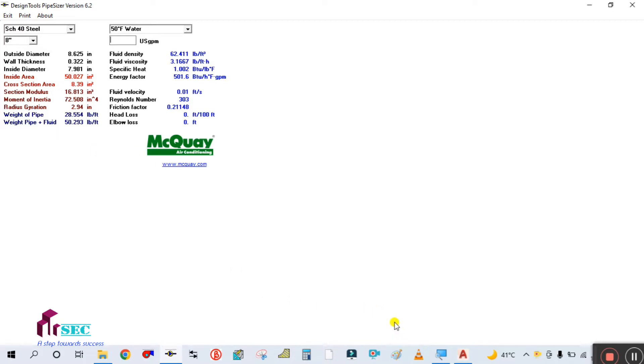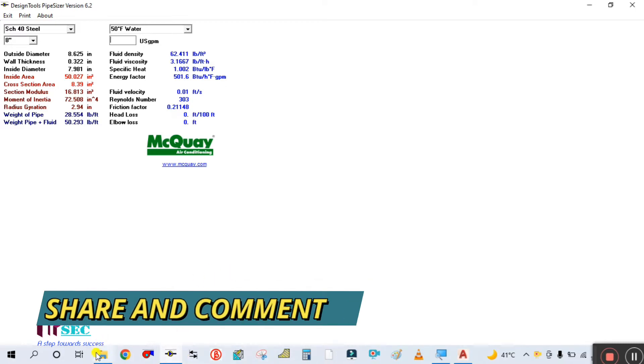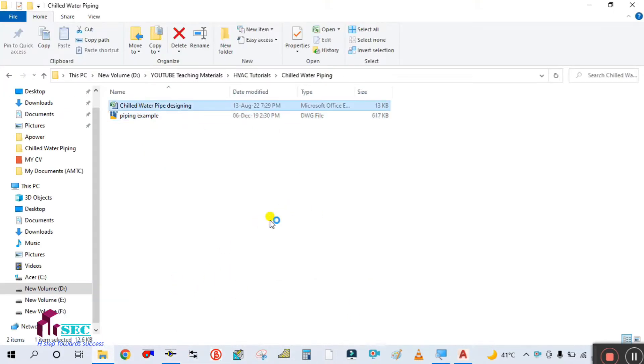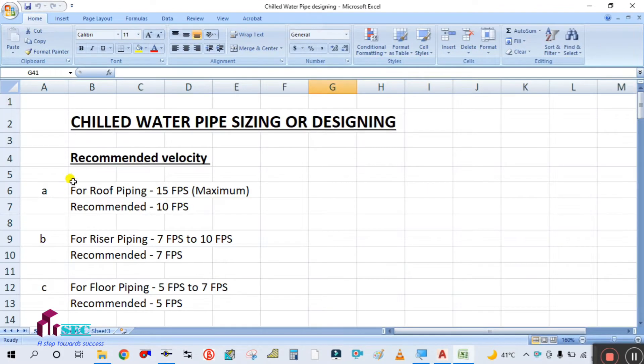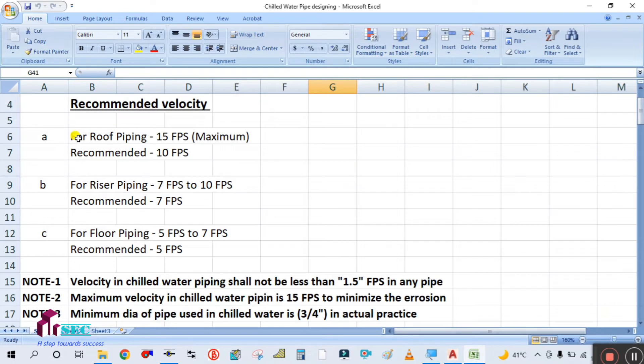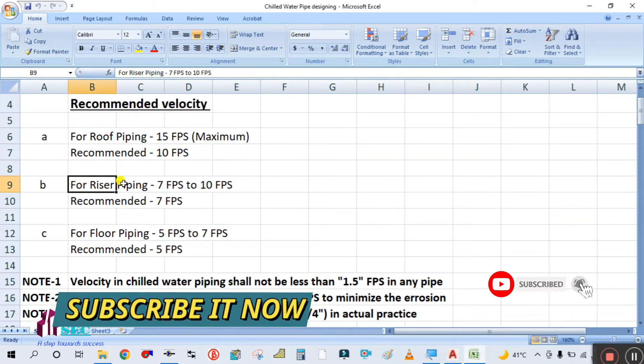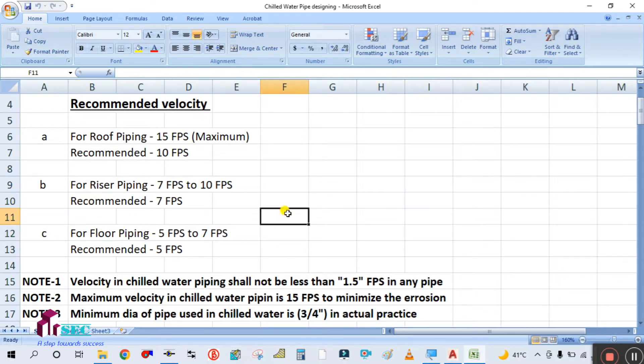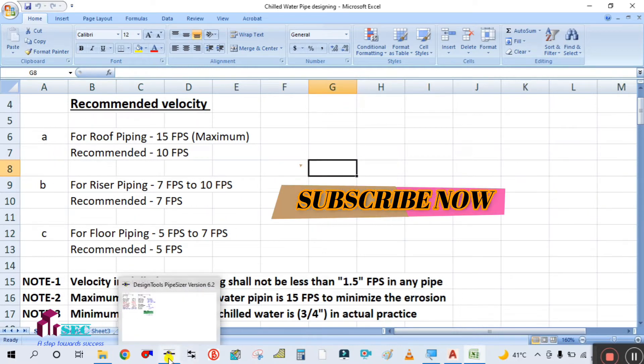In this velocity method you only need to look at the velocity. Let me open this Excel. You can see here in the velocity method: for roof piping the maximum velocity is 15 feet per second and recommended is 10 feet per second; for the riser it's 7 to 10 feet and recommended is 7 feet; and for floor piping it's 5 to 7 feet. So you only need to look at this velocity in the software.